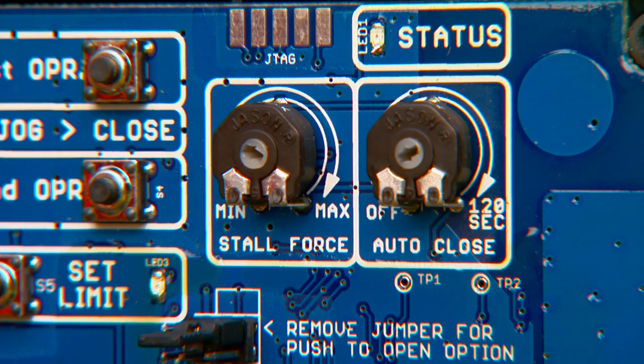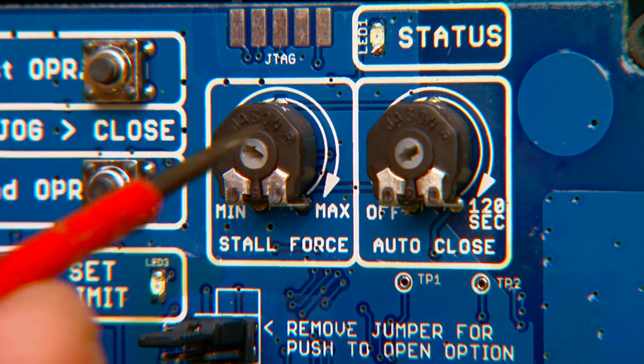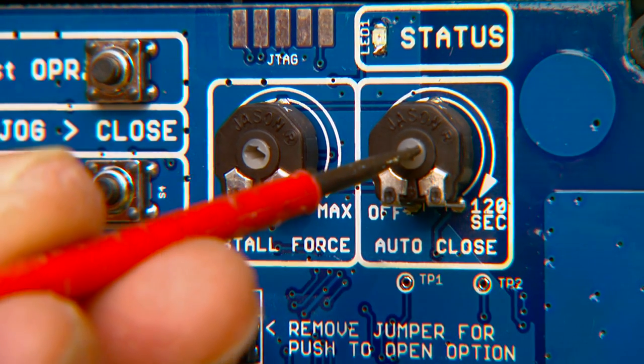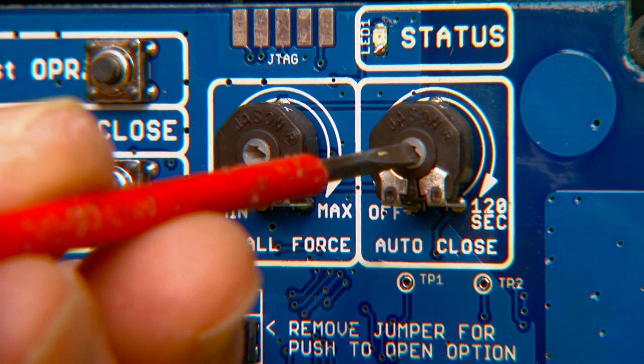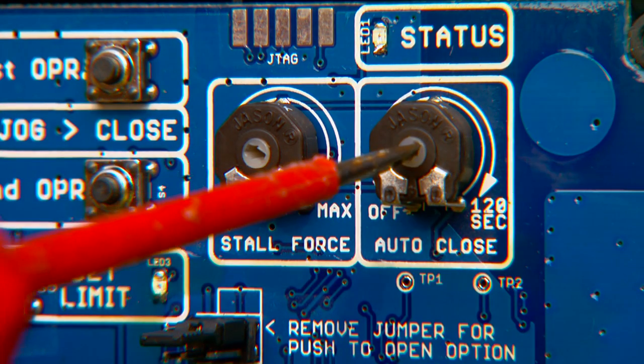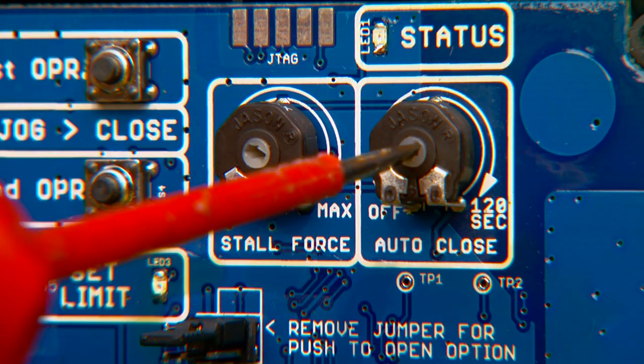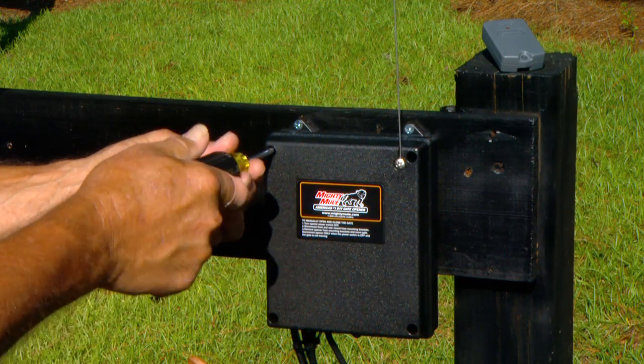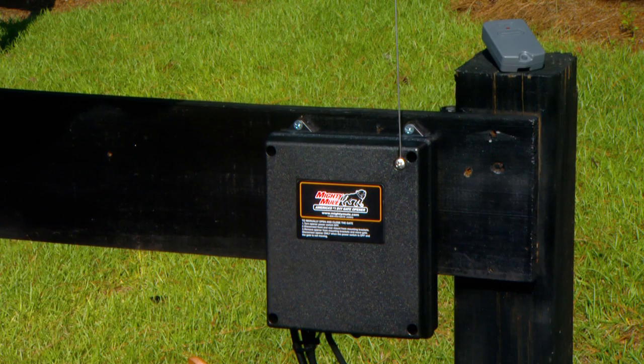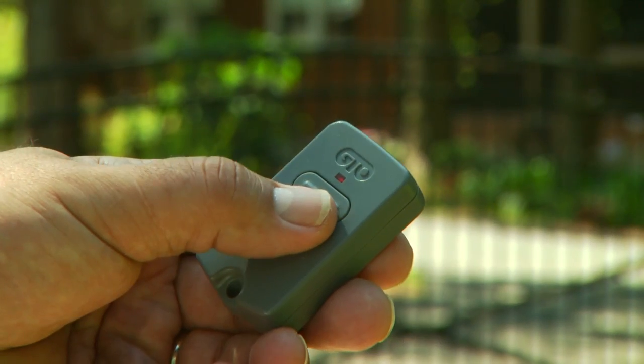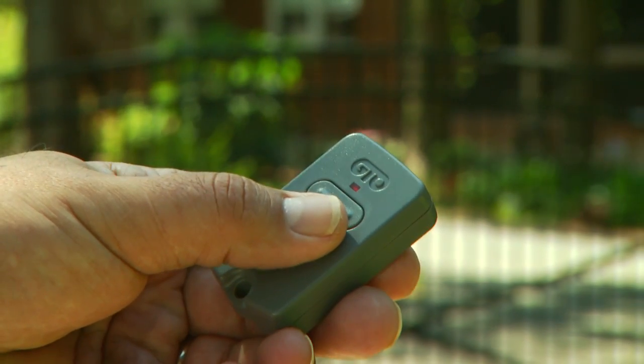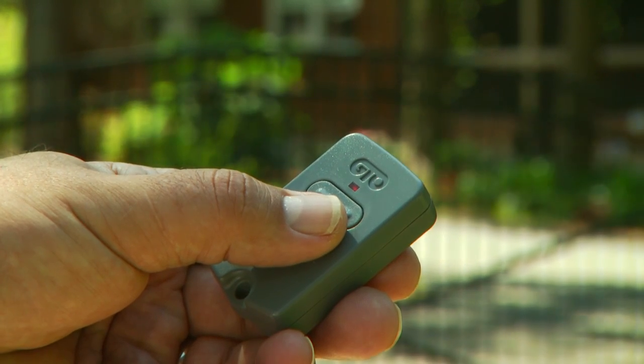The auto-close setting determines how long the gate will remain open before automatically closing. The factory setting is off. You can adjust the auto-close time to off or from 3 to 120 seconds. Replace the control box cover. You can override the auto-close setting by pressing the transmitter button to make the gates close immediately.